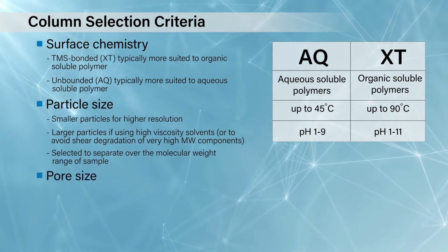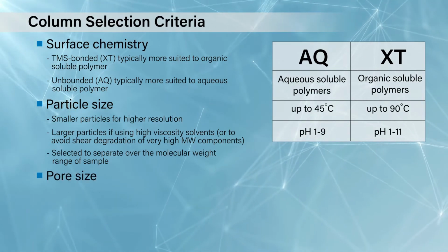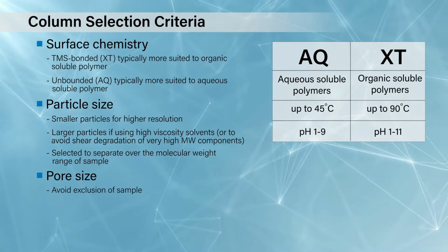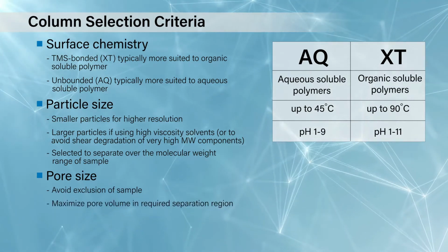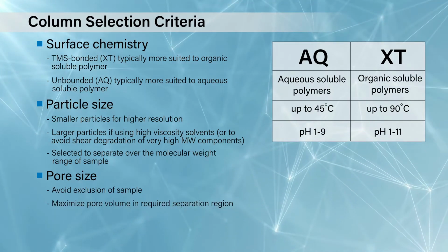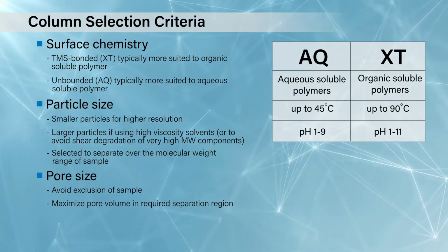With the pore size, there's a variety of pore sizes available, and you will optimize this to your molecular weight distribution. We use individual pore sizes to maximize the resolution obtained, but this means if you have a broad polymer distribution, then you may need to make a bank of different pore sizes to cover the full molecular weight range.